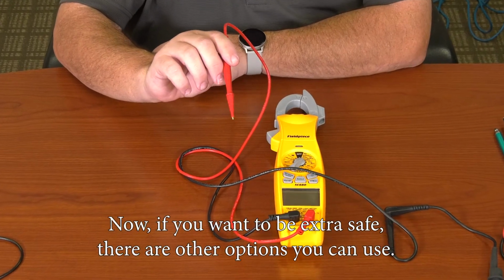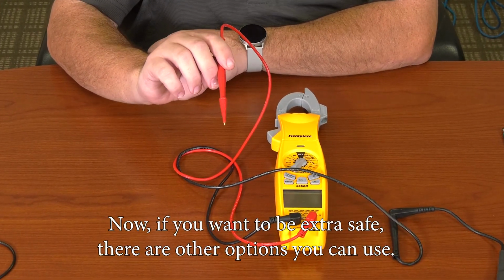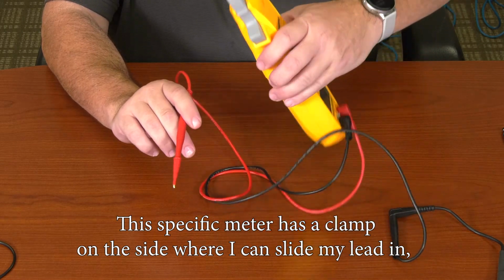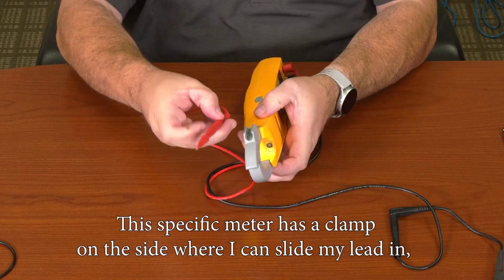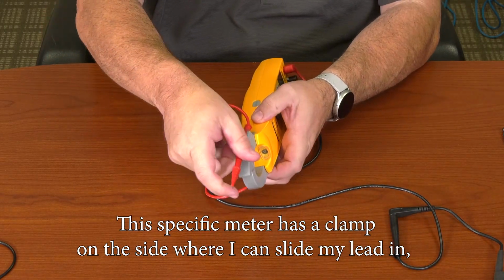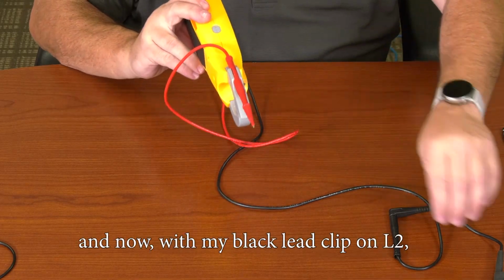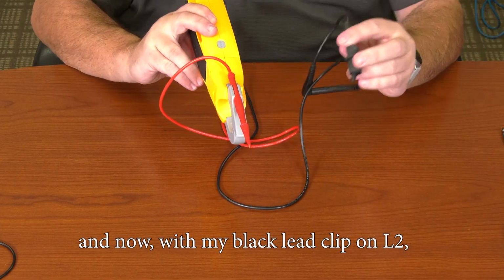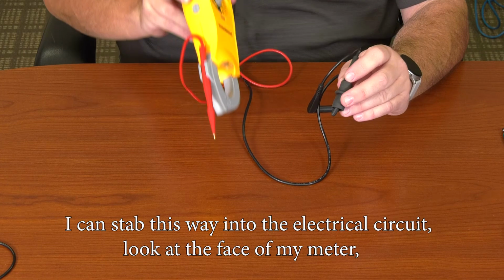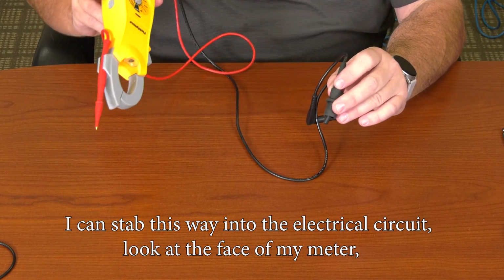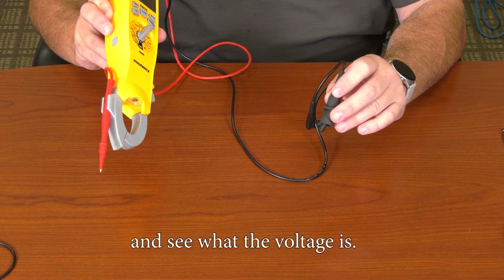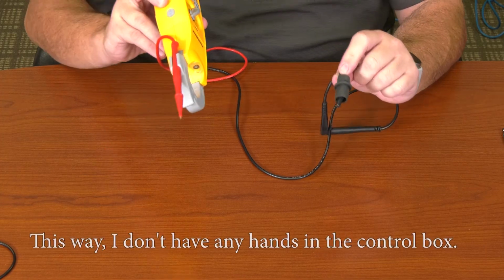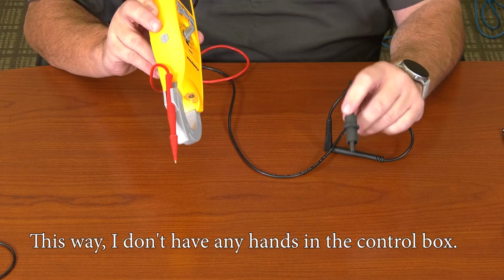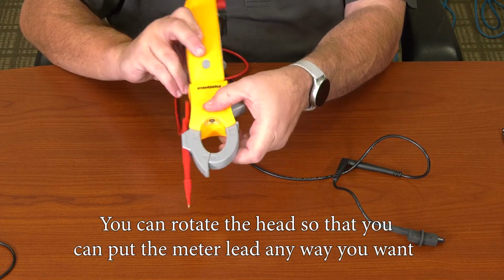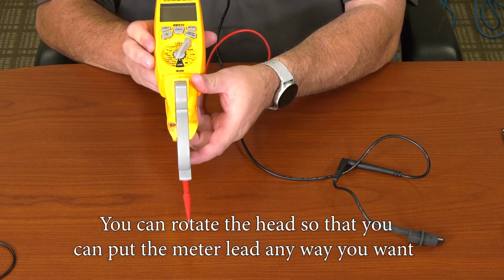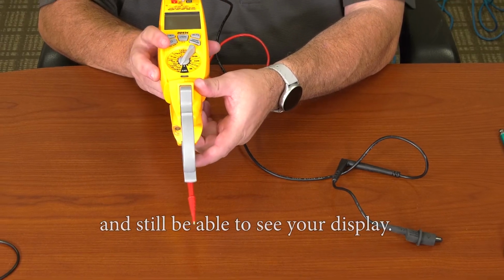Now if you want to be extra safe, there are other options you can use. This specific meter has a clamp on the side where I can slide my lead in, and now with my black lead clipped on L2, I can stab this way into the electrical circuit, look at the face of my meter, and see what the voltage is. This way I don't have any hands in the control box. You can rotate the head so that you can put the meter lead any way you want and still be able to see your display.